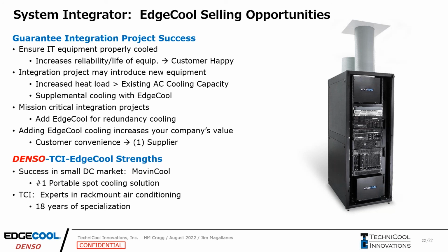Yep. And Jim, I think this is Rick from Thermobond. I have a question. What's available on alarm and reporting for remote monitoring? Is there something available within the product? Yes, we have some locations where you can hook up to the building management system. You send it alarms if something's happened to the unit, or shut off the EdgeCool unit if, say, there's a fire within the building, something like that. That's what we have right now.